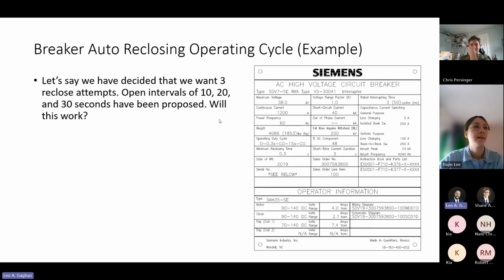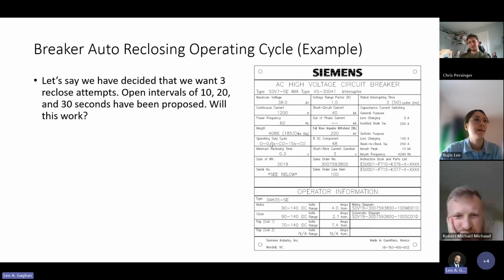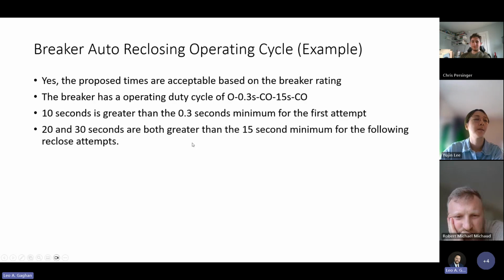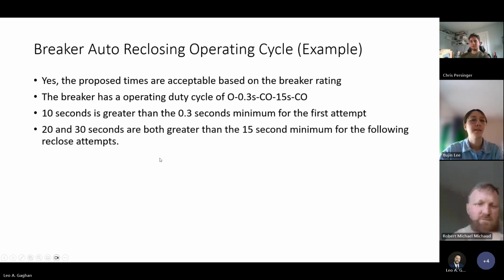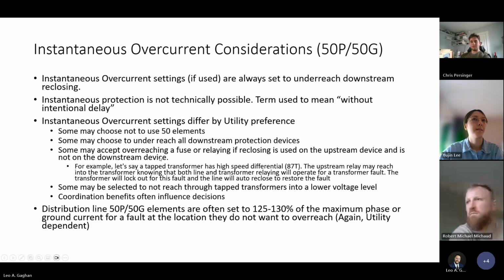So this one should work, right? That 10 seconds is greater than our 0.3 minimum time, and then 20 and 30 seconds are both greater than the 15 second times for the following reclose attempts. So yes, the proposed times are acceptable. Okay.